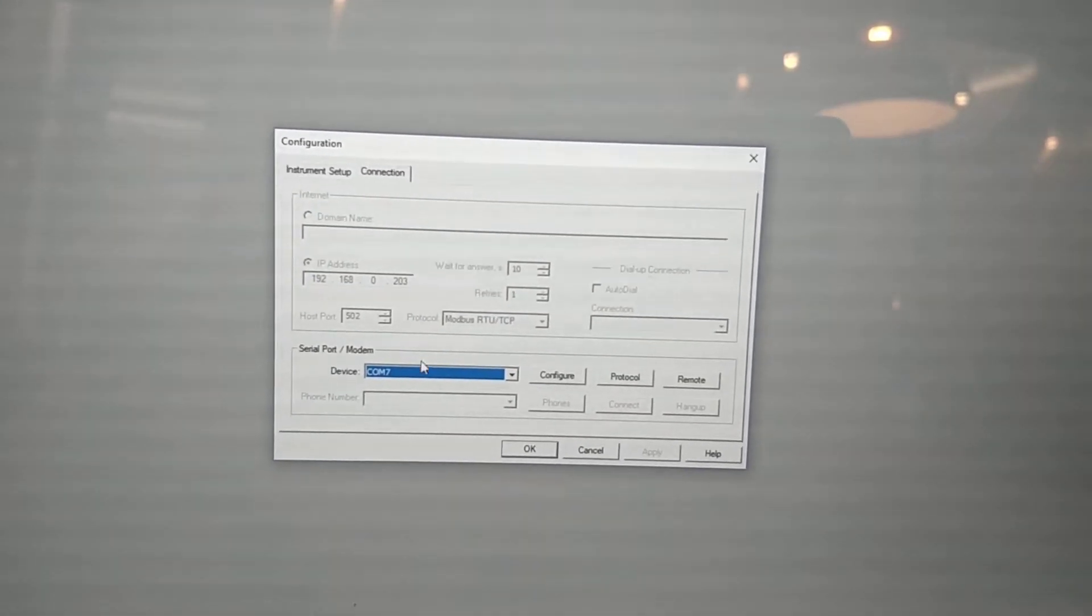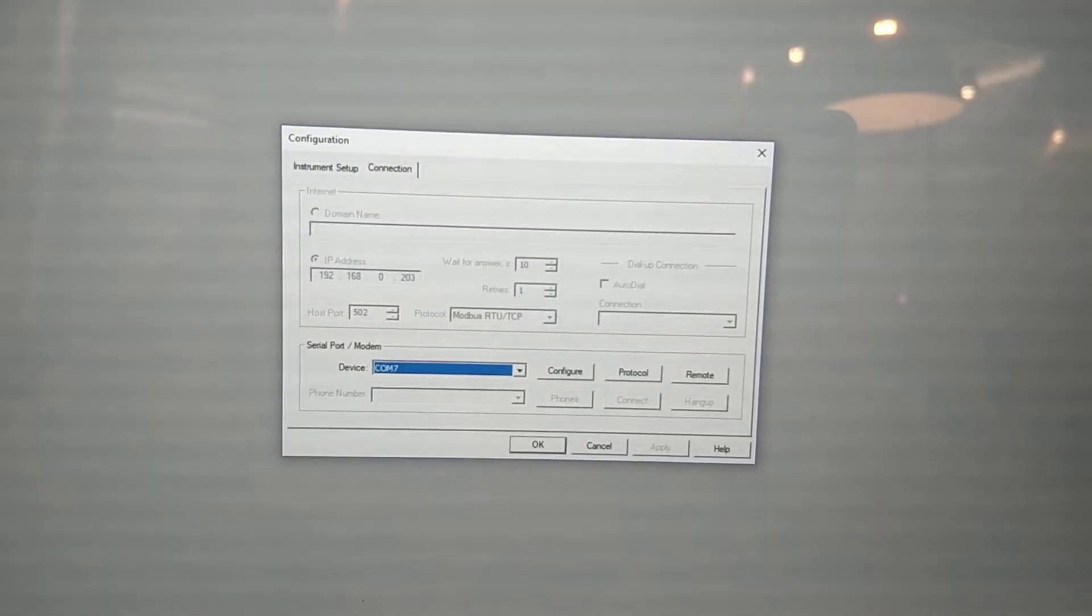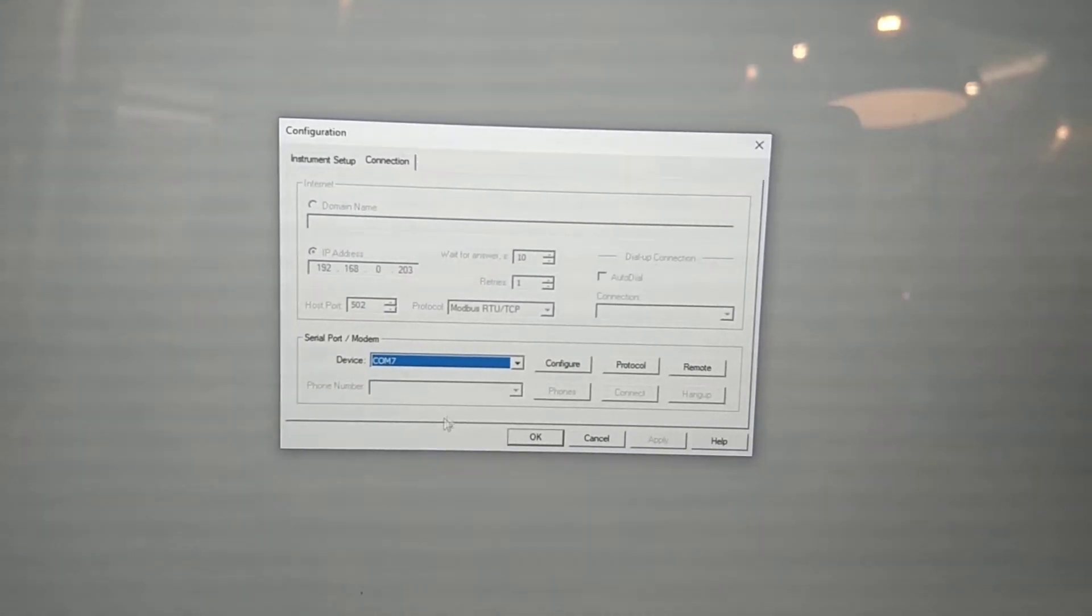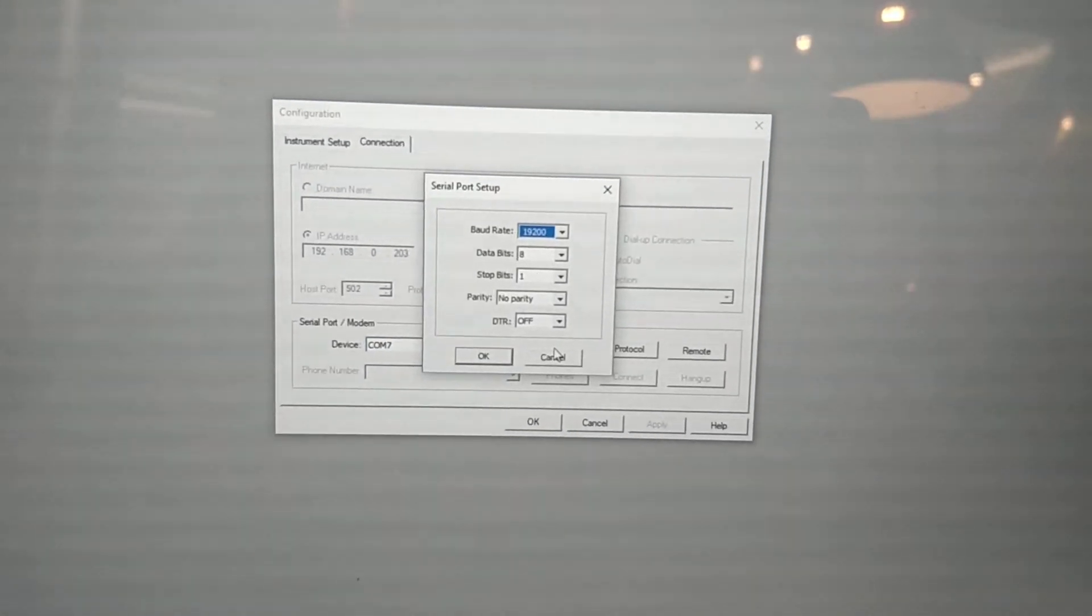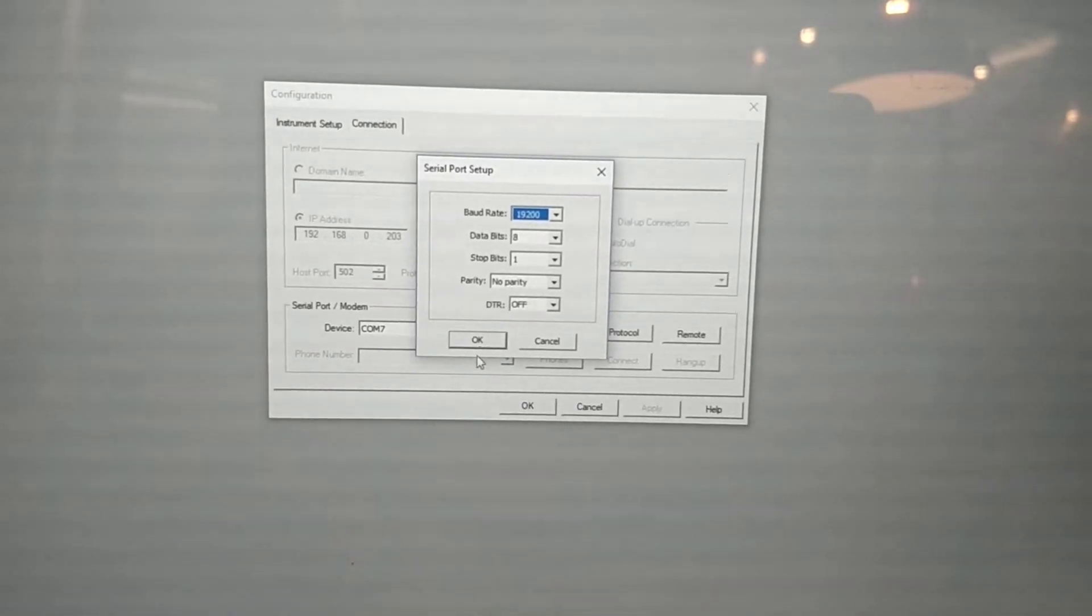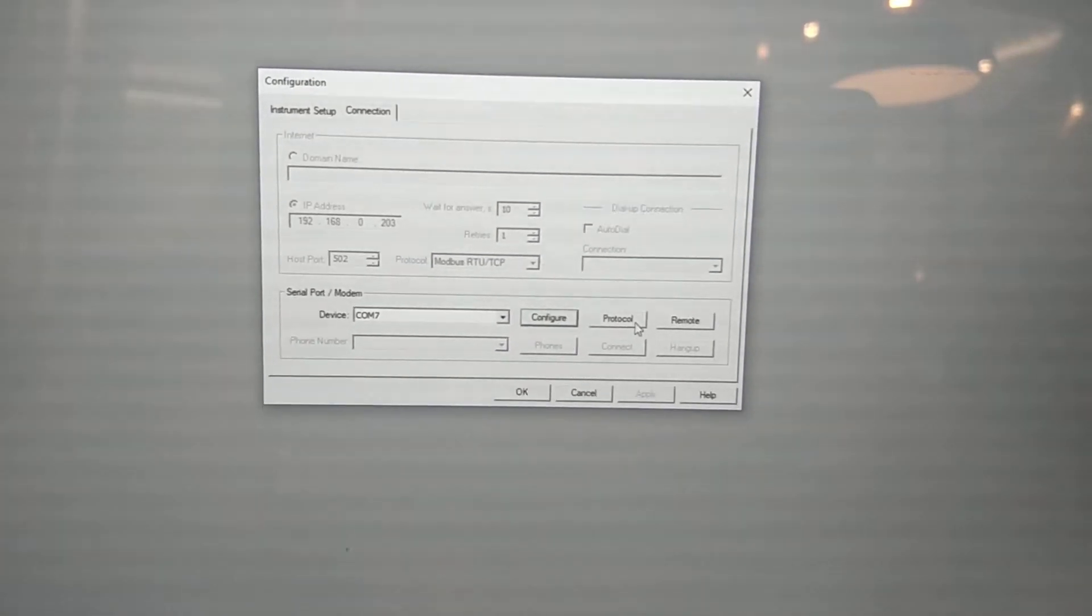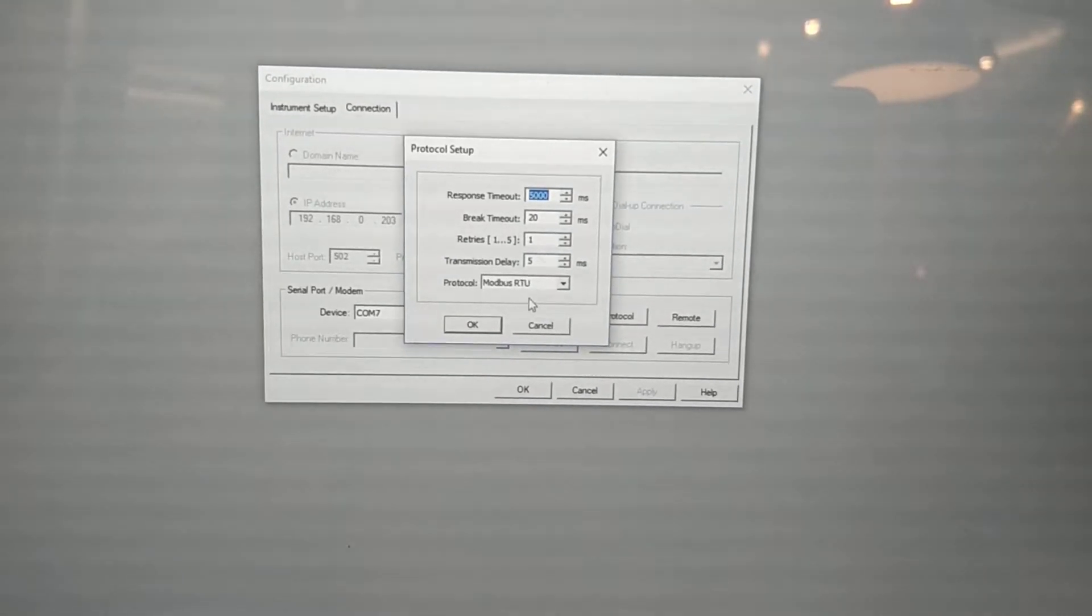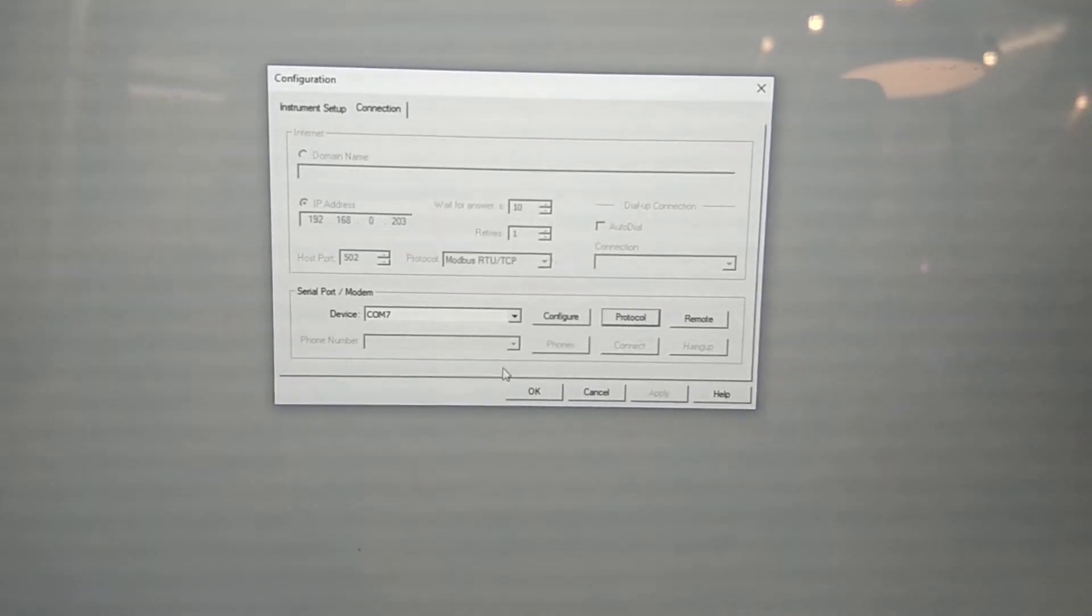You're going to have your COM7 which has been assigned in your PC for the USB converter. You're going to have a baud rate of 19200. And you're going to have a protocol of Modbus RTU. You're going to hit OK.